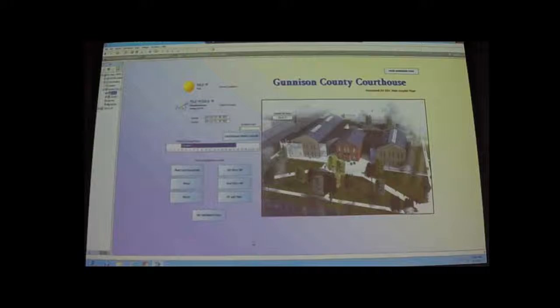How far back can I see trends, like if I want to see a history, make a report? You can set those up for literally infinite. They're being collected on the supervisor. If your trends are being collected in the Jace itself, in the blue cabinet, then you're limited. Okay. Depending on how many points you have, there's a calculator for that. But if you're doing your trending on the actual supervisor, you can tell it how long you want to see.